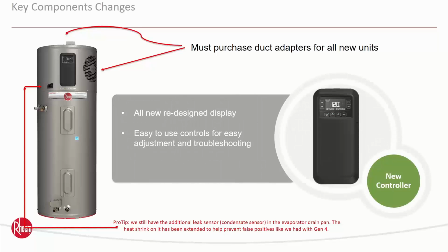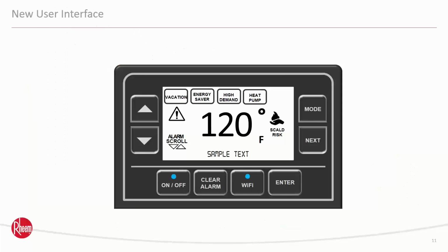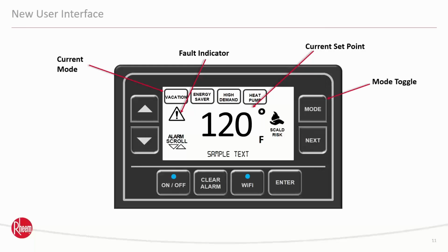Like I said, the display on our new unit is generation 5. It's a touch button display, where before it was a touch screen. It's a lot more user friendly and easier to use. We'll talk about that here for a second. You've got a mode indicator, and there's 5 modes on this heater. We'll talk about that. Fault indicator, your current set points. This is to toggle between your modes. Told you we have 5 modes. It does have a scald warning. Once you get to 120 degrees or above, that little icon's going to flash there and stay on the screen and let you know that you're at a scald situation now, if you're running straight hot water.